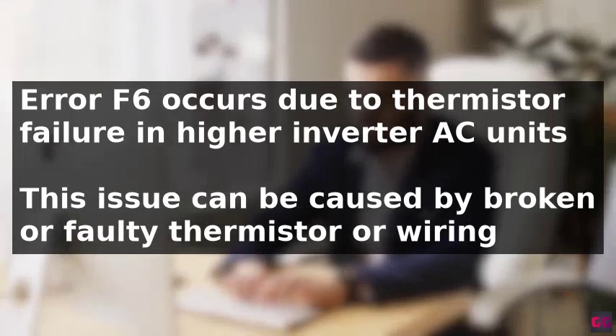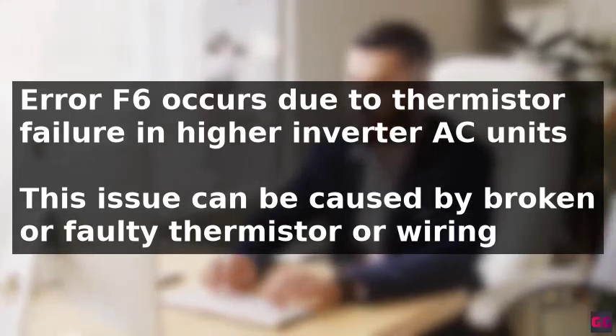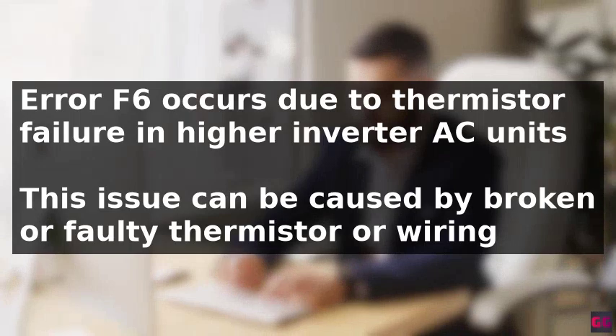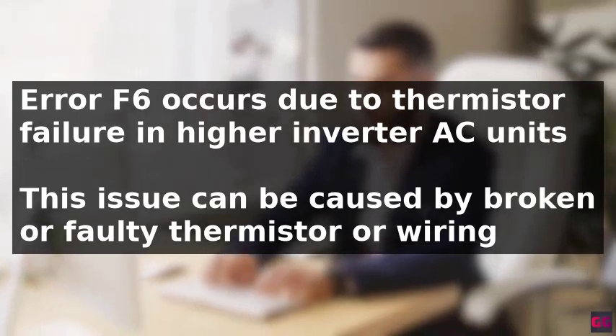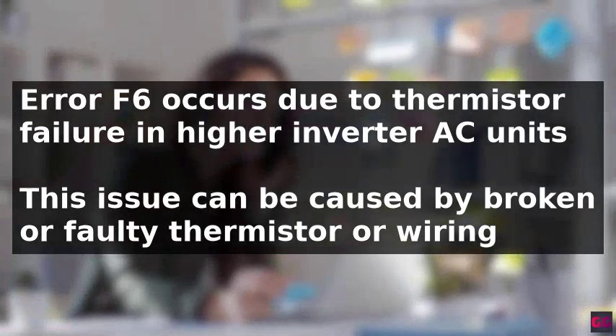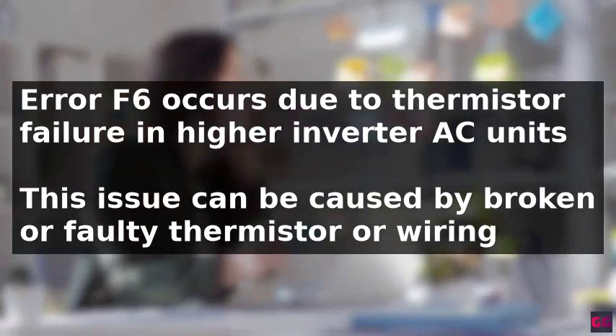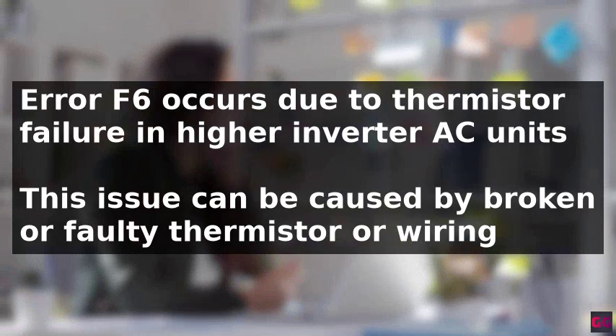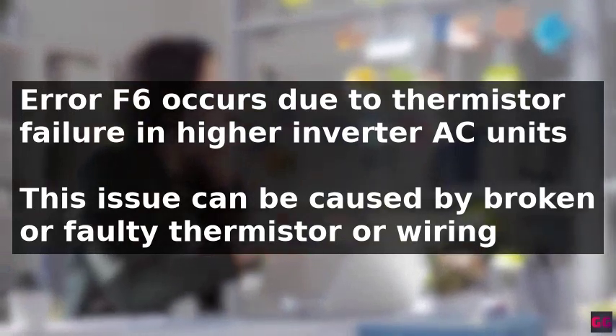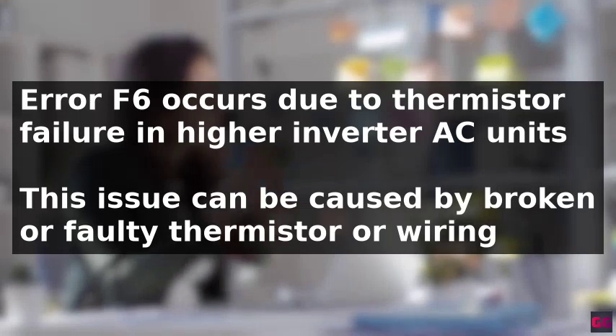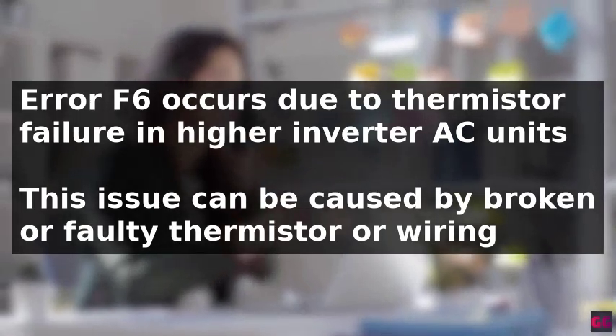Error F6 in higher inverter AC units is a thermistor-related abnormality that occurs due to the failure of the ambient temperature sensor. This issue can be caused by a broken or faulty thermistor, faulty wiring, or a faulty printed circuit board (PCB).